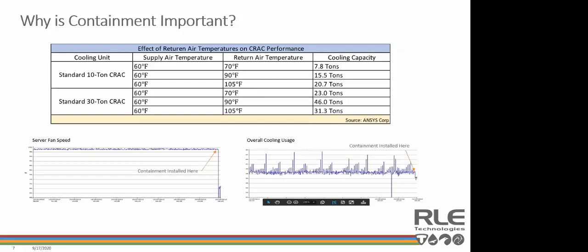The graph at the bottom of the screen shows a measured reduction of 30% in server fan speed and a reduction in overall cooling energy from 37 kilowatts to 33 kilowatts after cold aisle containment was installed in one data center. Now, we'll talk more about ROIs involving containment projects later on during this presentation, but most customers can easily expect to see a 20 to 30% savings in cooling energy after implementing aisle containment in their data centers. I'll hand it back to Tim now to talk about different types of containment.